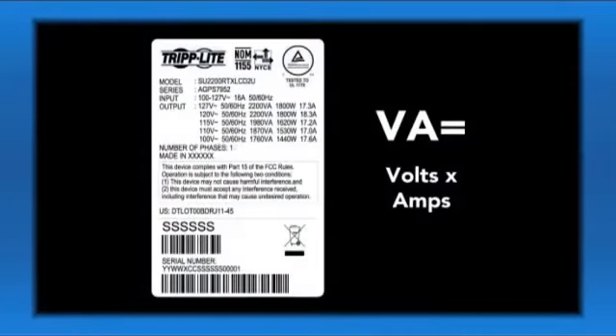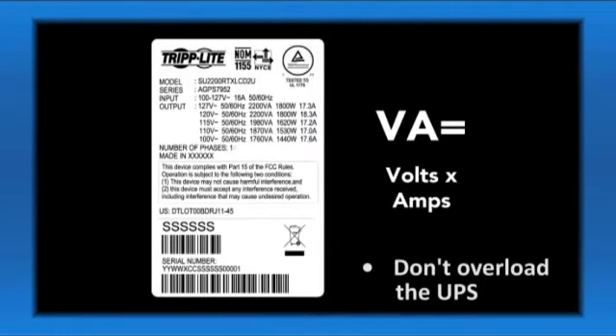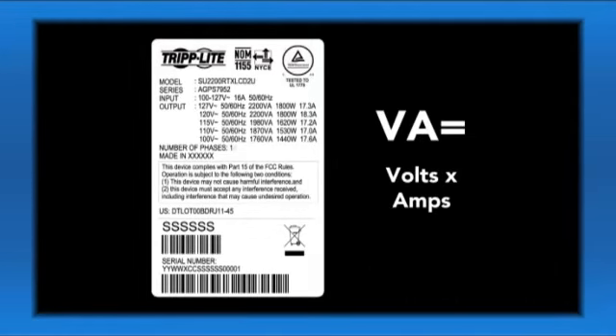Your UPS is designed to support electronic equipment only. Do not connect household appliances or laser printers. You will overload your UPS if the total VA rating for all equipment you connect exceeds the UPS's output capacity. To find your equipment's VA ratings, look on their nameplates. If the equipment is listed in amps, multiply the number of amps by the input voltage to determine the VA.